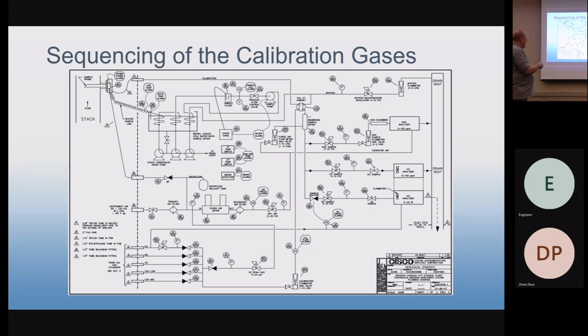So your timing relates to how long it takes this calibration gas to get up the calibration line, get into the probe, come back down the sample line, and come over here and actually fill the analyzer. There's a time there. You can't make it any shorter than the physics requires. You can increase the flows, and that'll speed it up a little bit. But on the other hand, you're also spending calibration gas. So it's kind of a balance, you know. How quick do we want this calibration to happen? How often do we want to change our cylinders for our daily cals? So there's a balance point on that.